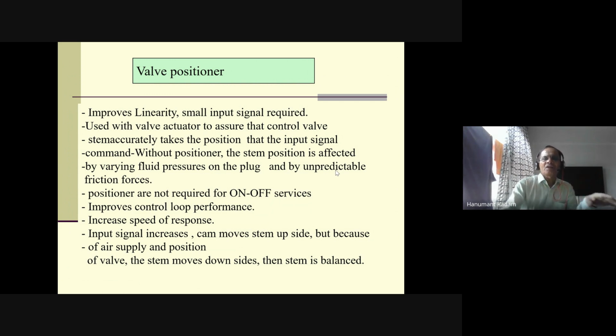So if you see here, with a positioner you get the control valve stem accurately taking a position as per controller requirement. However, without a positioner, the stem position is affected by varying fluid pressure on the plug and by unpredictable friction losses. It means if the positioner is not there, then you will not get a controlled pressure. Suppose at the input side the valve pressure increases, it will automatically lift the stem. So we cannot say it is control. So for controlling flow and pressure, the valve positioner is required.